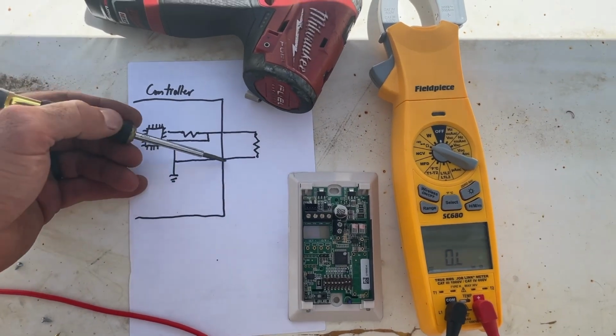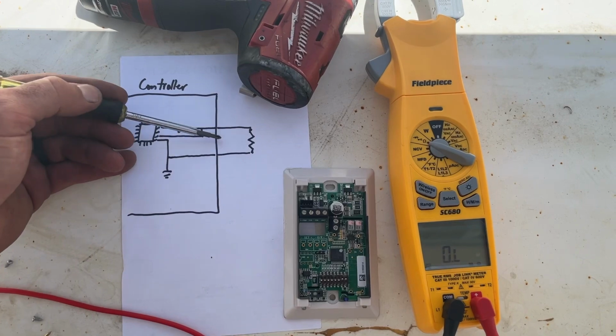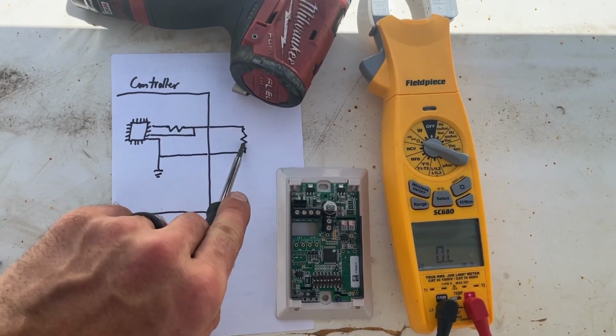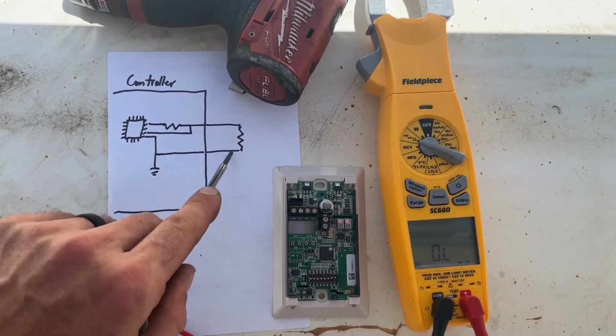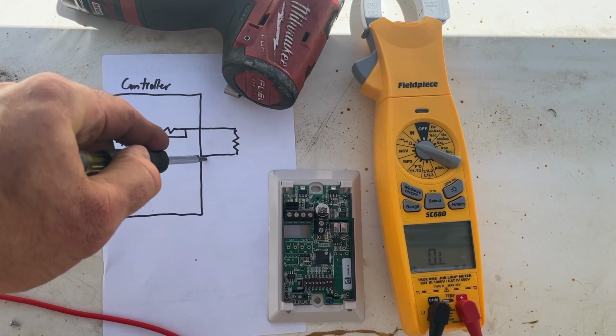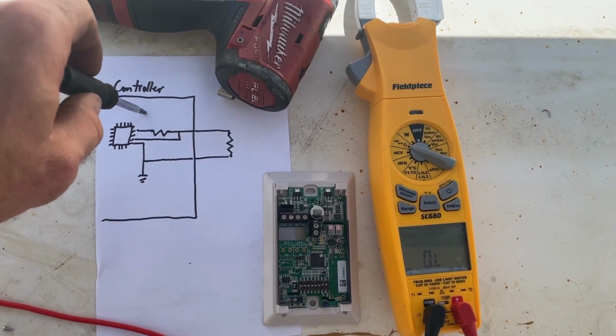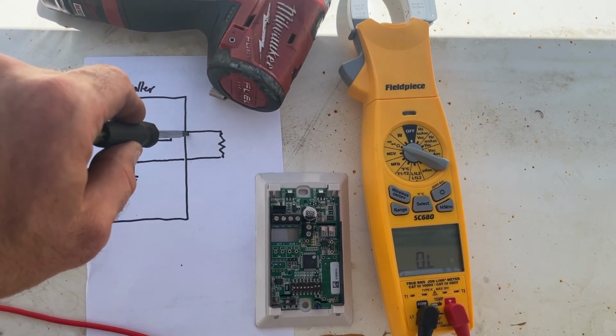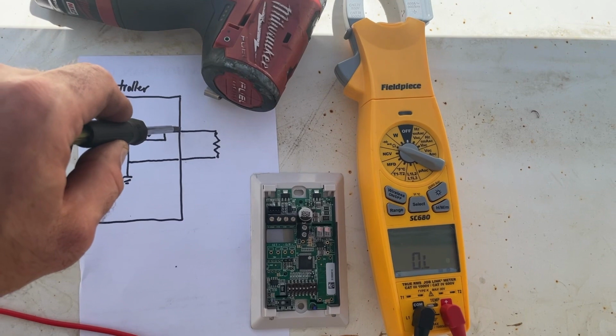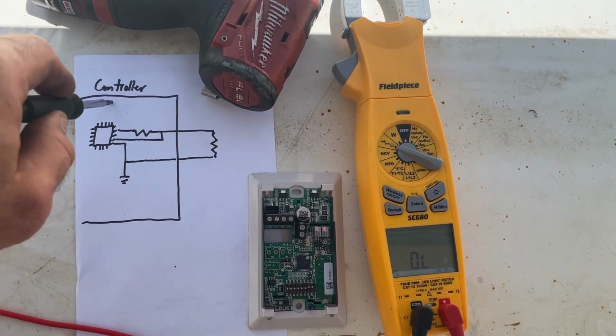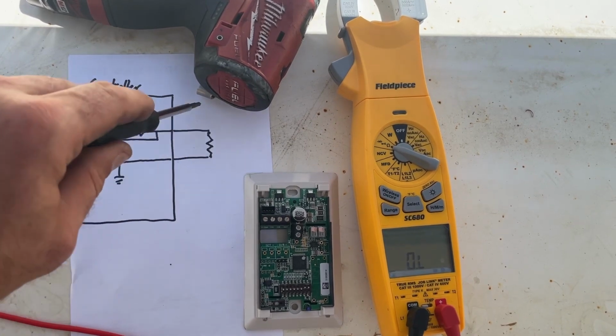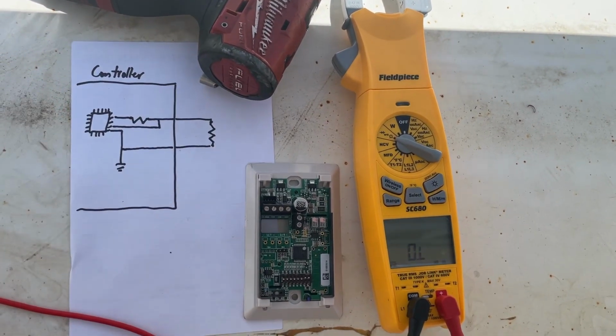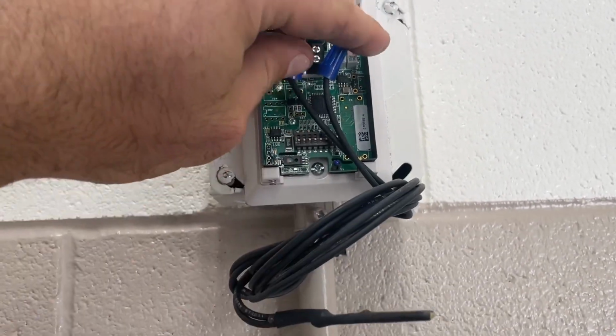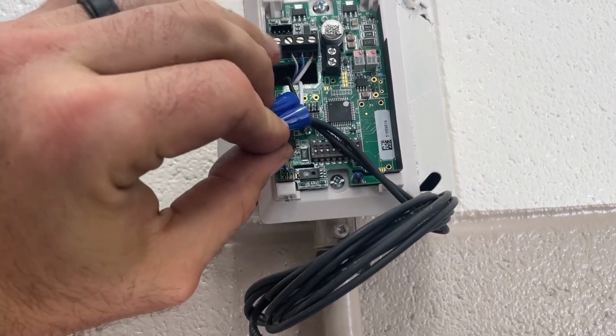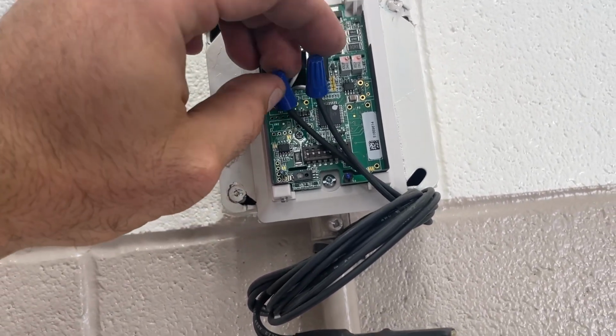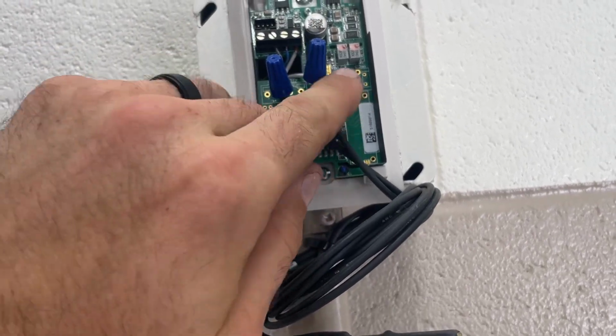For example, if you went up to this connector in red, 3.3 volts, then you would know that either the thermistor is open or you've got an open wire. If you go up here and you were to read 0 volts, then you've either got a bad controller or you've got a short. So you unhook one wire, and if your voltage jumps back up to 3.3, your controller logic is good, and you've got a short down here. You see how understanding this circuit can greatly help your troubleshooting. Here's the sensor here, which went in place of these wires being connected here, which is where this thermistor feeds up to.